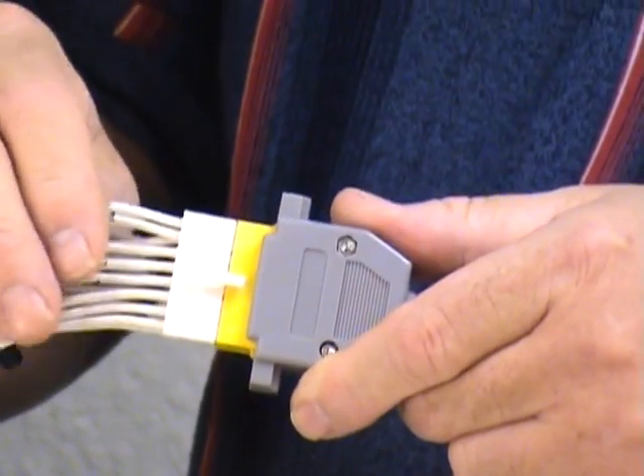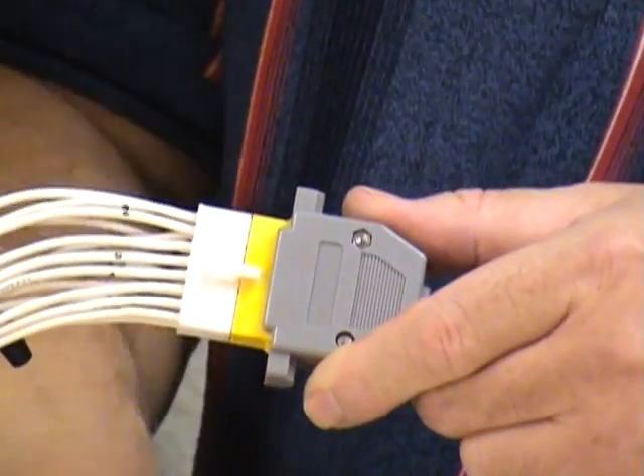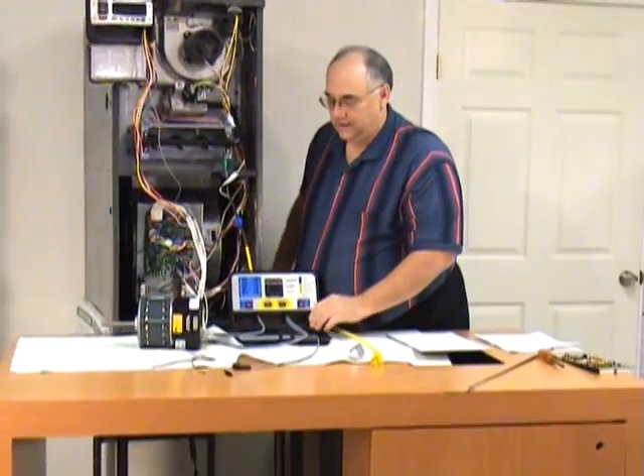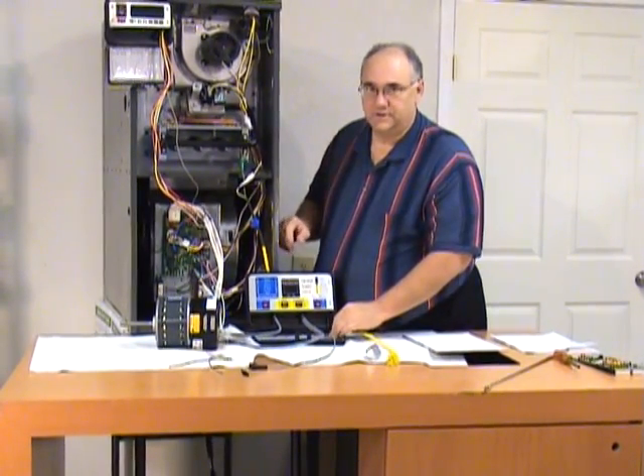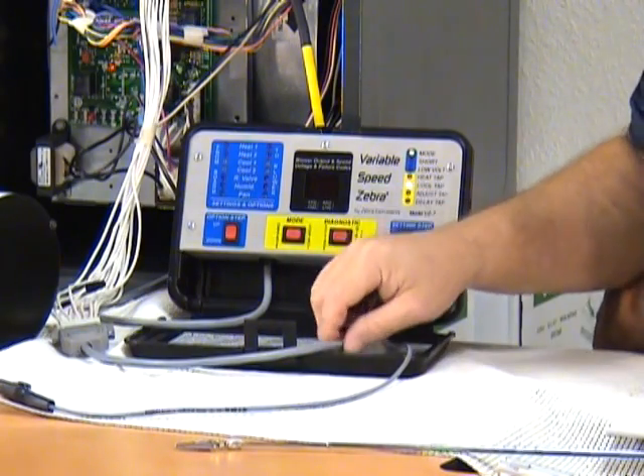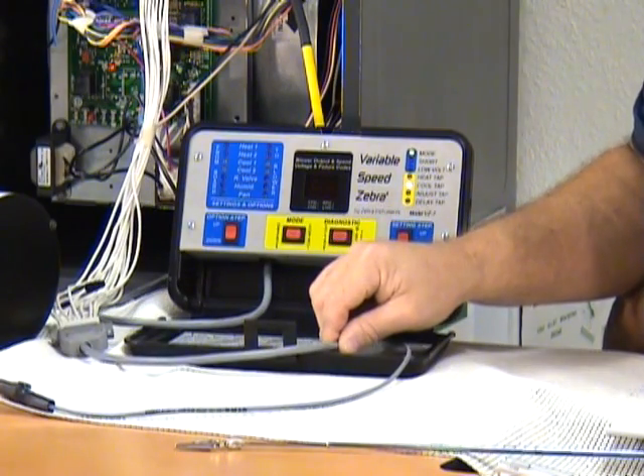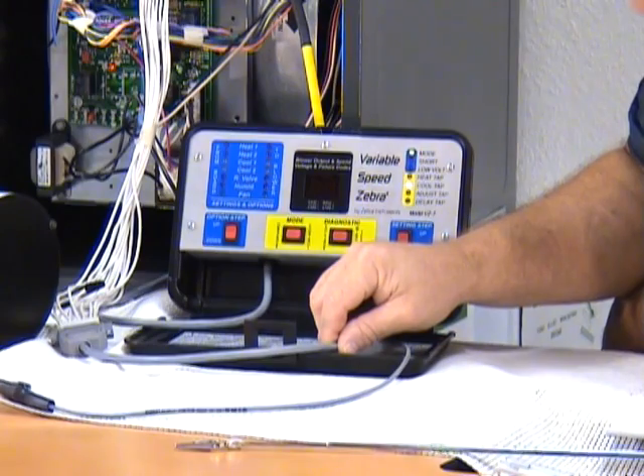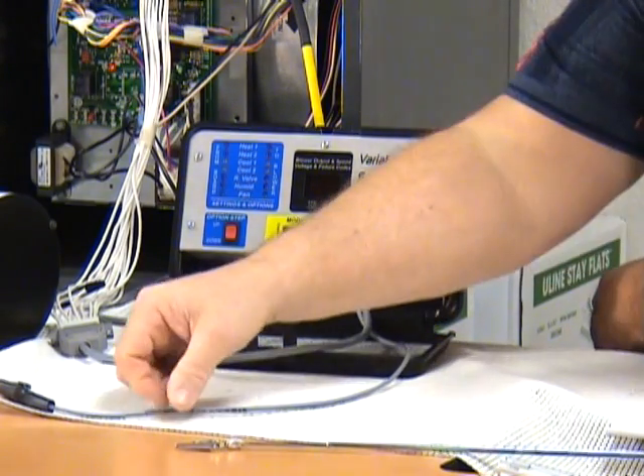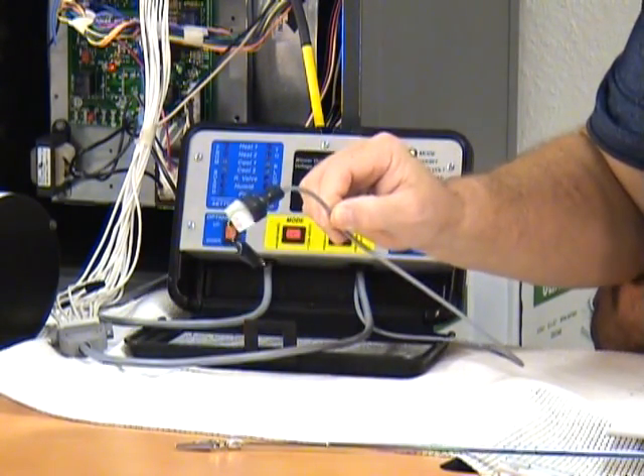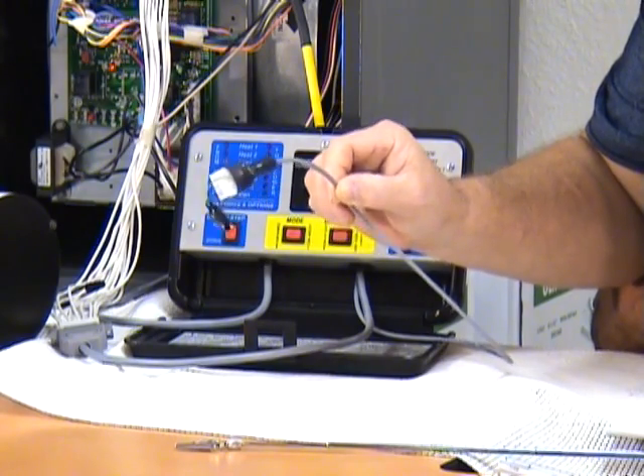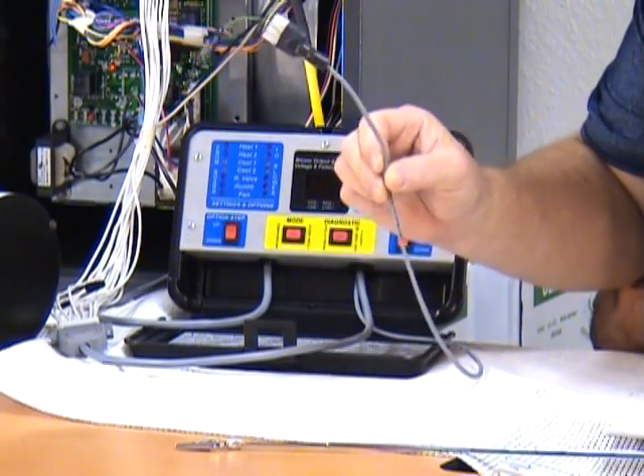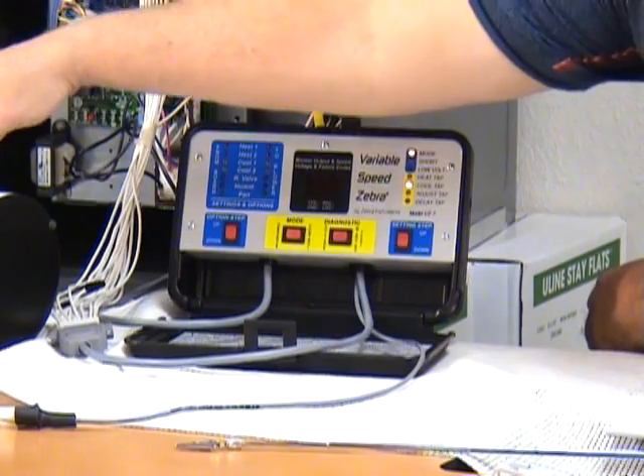We've already connected the blue harness to the motor because it's so hard to picture it. So we went ahead and did that before we started running the camera. And we've hooked up the power connector to the motor. After you've hooked up the two main harnesses of your Variable Speed Zebra to the furnace or the air handler and the motor, turn your power back on. Oh, by the way, this small cable here, it's not necessary to hook it up at this time. It's only good for one thing, and that's testing this section of the motor.